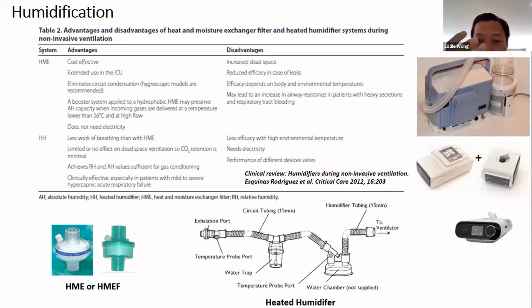When we exhale, the exhaled air contains heat and moisture, so it will be retained inside this HME. When new air comes in from the ventilator, the air will be reheated and re-moisturized before it goes into the airway. If you ask me which way is more effective to promote humidification, I will say for tracheostomy patients and pediatric patients, an active humidifier is always highly recommended. For the Trilogy, we do not supply the humidifier. This is a third-party humidifier. For the rest of the life support ventilators, we do supply the humidifier, which you can assemble together with the ventilator device.